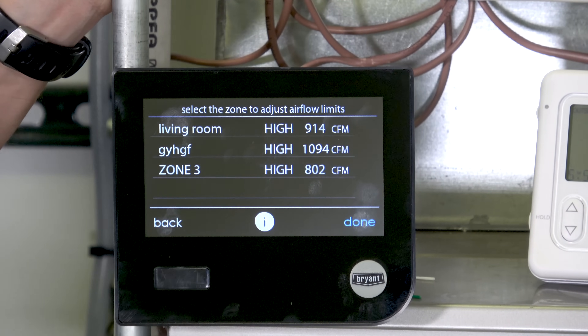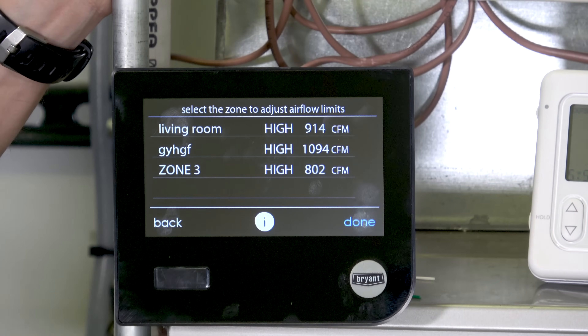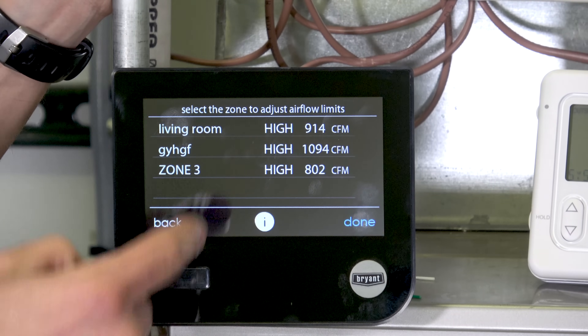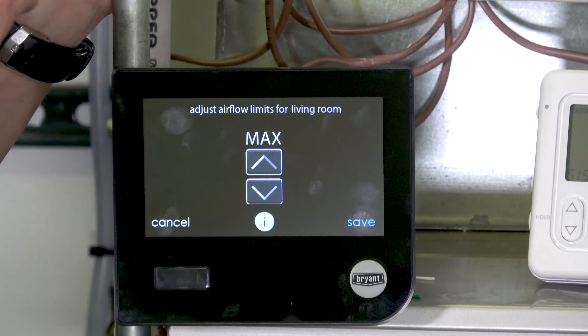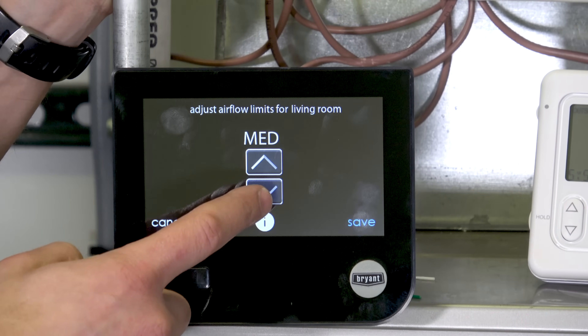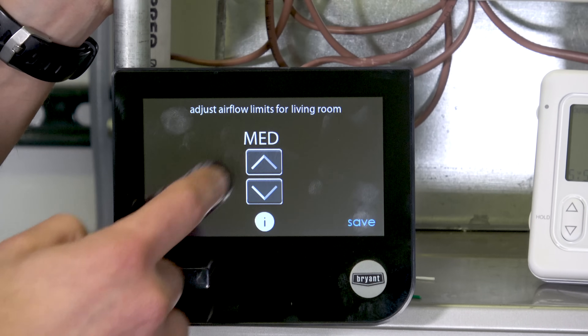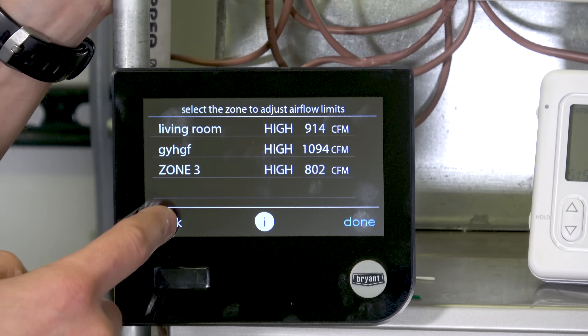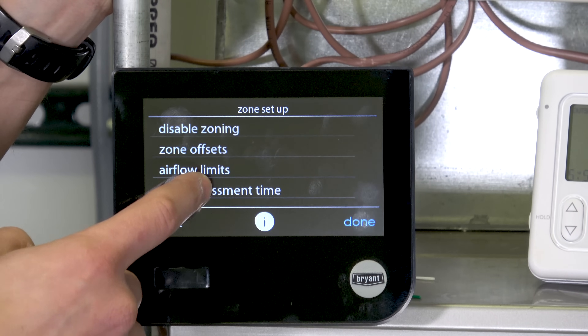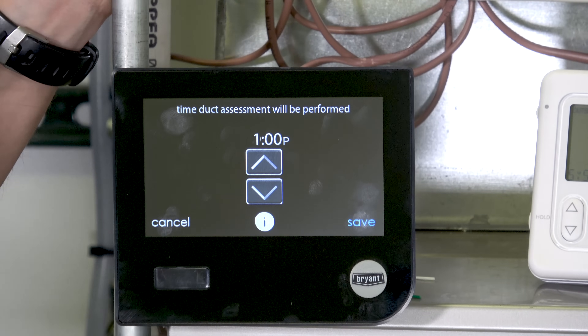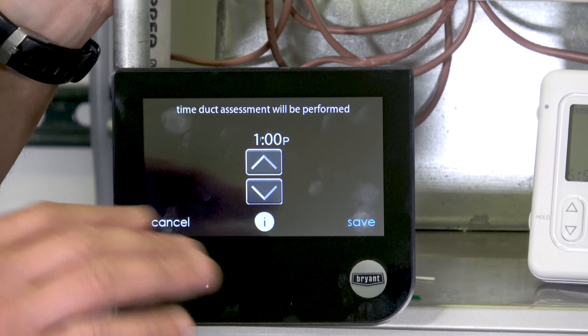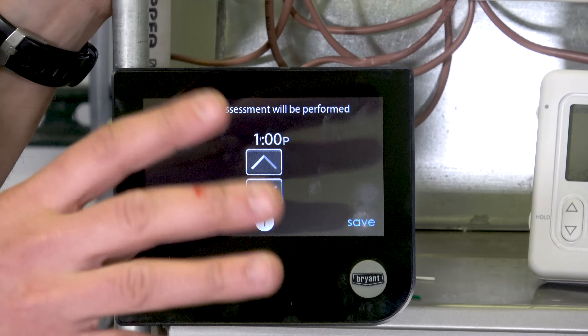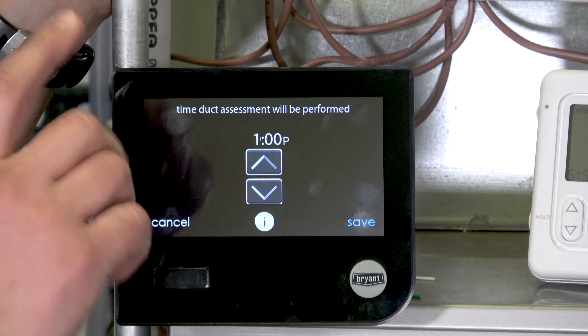I also have airflow limits. Right now they're all set to high, and it shows the CFM that correlates to. I can go into any zone — the living room zone for example — and adjust from max down through high, medium high, medium, medium low, low, and so on. So if I'm getting too much noise I can adjust those here. I can also adjust the duct assessment time — by default it runs at 1 PM. When the system first came out in 2005 it ran at 1 AM, which wasn't great since people were sleeping. Now 1 PM is the default since most people are at work, but you can change the time if the customer prefers.